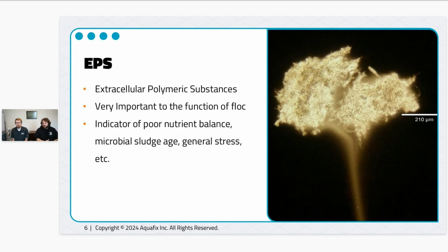As far as the biological performance, it's a little bit different with an MBR because you're existing at a lot higher solids concentration. So just in regards to having more solids within your mixed liquor, in some cases fivefold higher than what you would see in a non-membrane system, you're going to have larger floc structures because there's just more solids there.